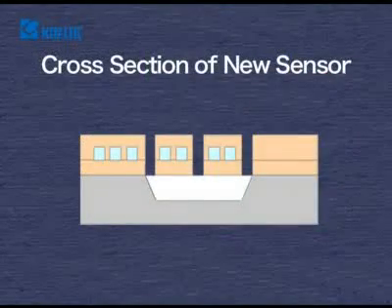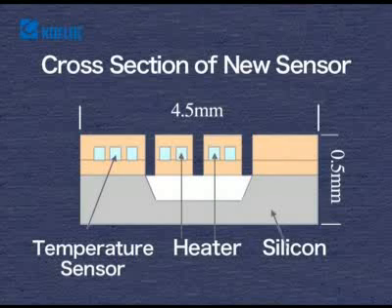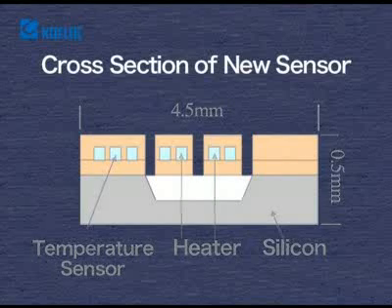A pattern diagram is used here to describe the sensing principle of the new flow sensor. When gas is not flowing, the output form of the model 7,100 sensor is a zero flow signal at that time.